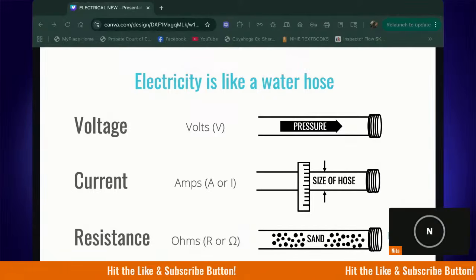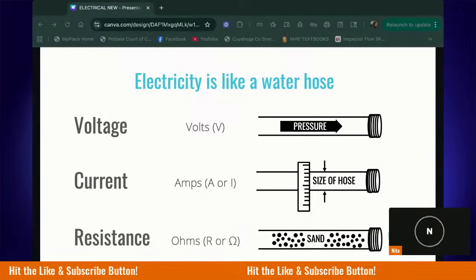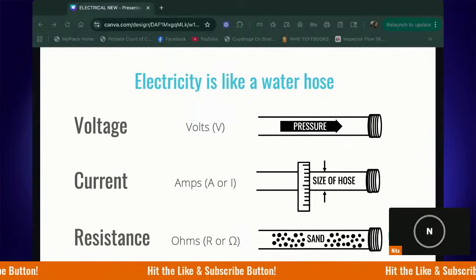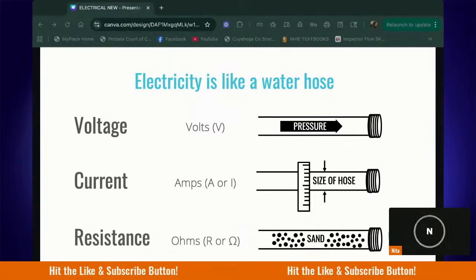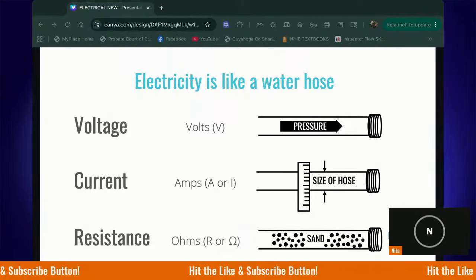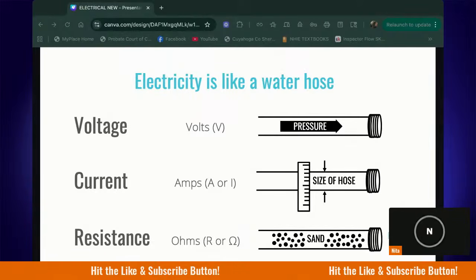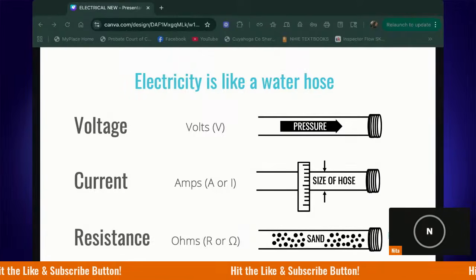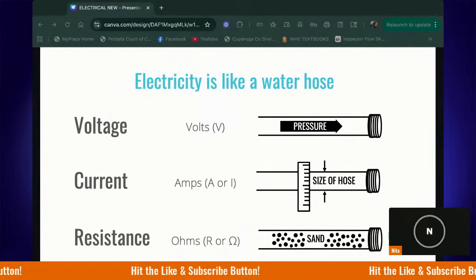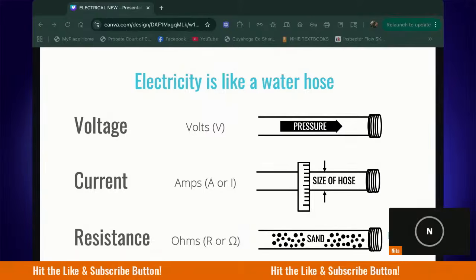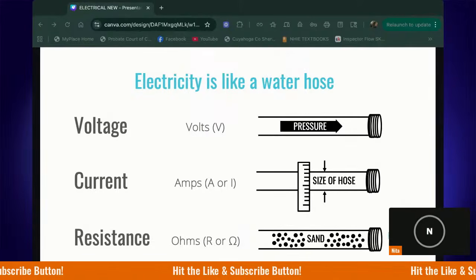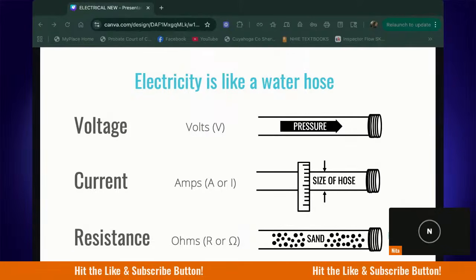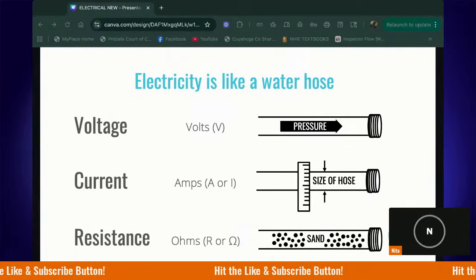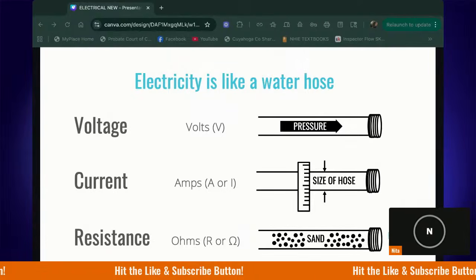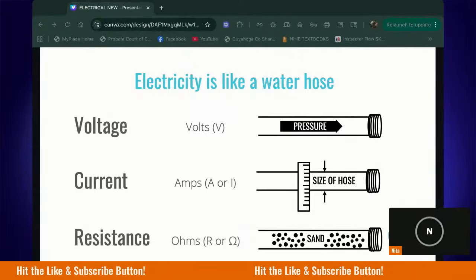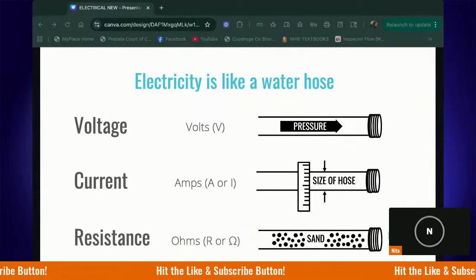So your breaker, your wiring, and your outlet have to be the proper size in order to handle the load. So that's one thing that we are looking to verify during inspections. Our breaker sizes, again, we'll talk about this on Friday, but say a 20 amp breaker, it has to match. There has to be a certain wire size that it uses. So we use a 12 gauge wire for our 20 amp breakers. Okay, so again, we'll get into that on Friday. But that is why current is important. Too much current, you'll have too much heat and you'll have a problem.